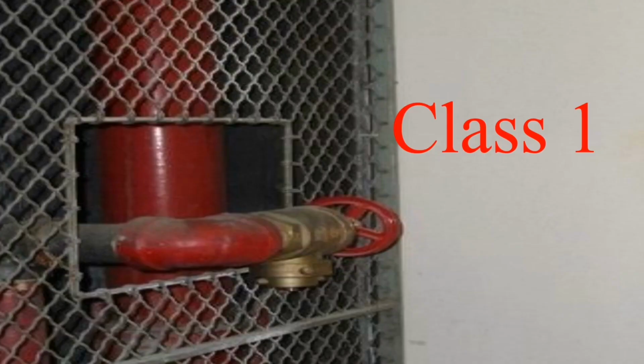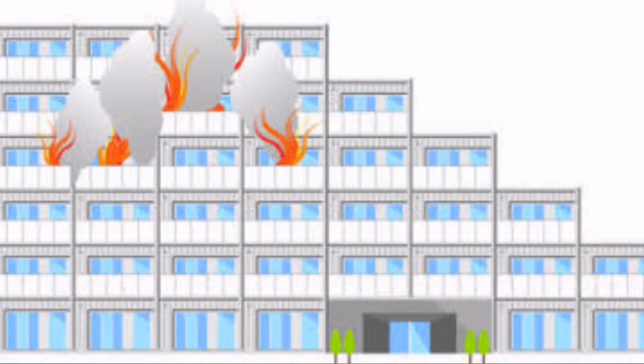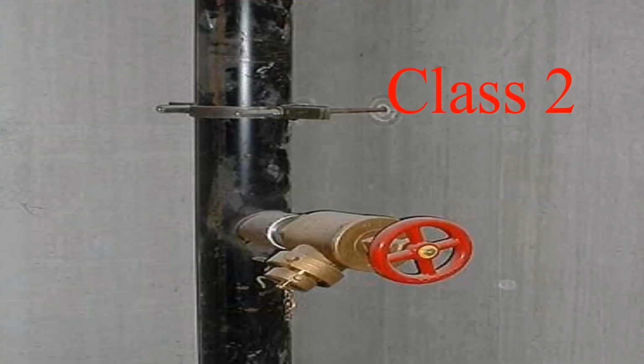There are three classes of the standpipe. Class 1 systems, 2-1/2 hose connections, are provided for use by fire departments and those trained in handling heavy water streams. In high-rise buildings without sprinklers and beyond the reach of fire department ladders, Class 1 systems provide water supply for the primary means of firefighting, i.e. manually. Class 2 systems, 1-1/2 hose lines, are provided for use by trained building occupants until the fire department arrives.